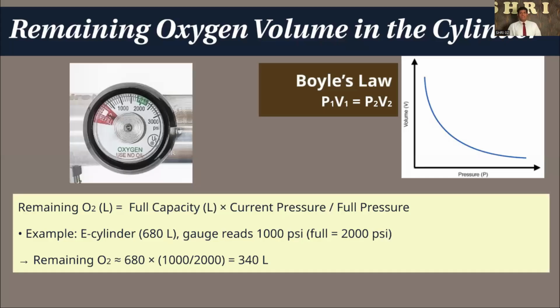If you connect A, B, C, or whatever the range, other than the jumbo cylinders, the gauge shows a pressure reading up to 2000. That is the pressure level, not the volume inside. But we can calculate the amount of remaining oxygen in the cylinder if we know the cylinder capacity and the current pressure level. So how can we do that?